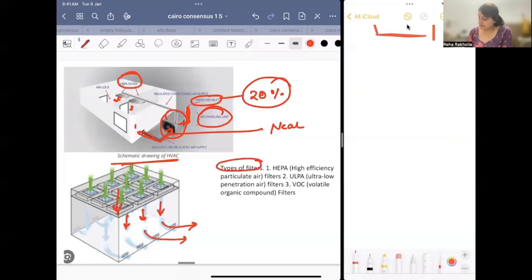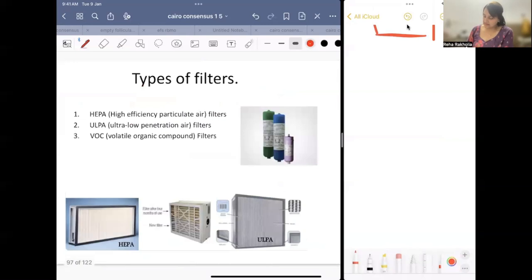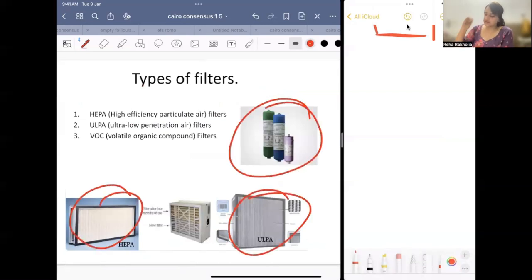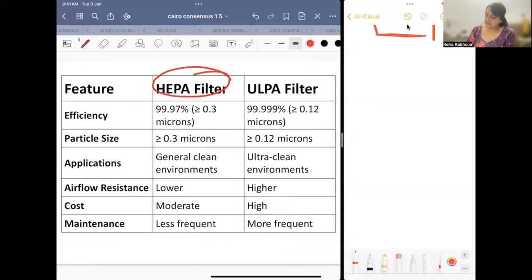There are 3 types of filters: HEPA filter, ULPA filter, and VOC filter. Okay. What is the difference between them? HEPA filter is high efficiency particulate air filter. ULPA filter is ultra low penetration air filter, and VOC filter is VOC. So this is the HEPA filter, this is the ULPA filter, and this is the VOC filter. This is an inline filter, an inline VOC filter. Okay. HEPA filter efficacy is lesser than ULPA. ULPA is even more efficacious.